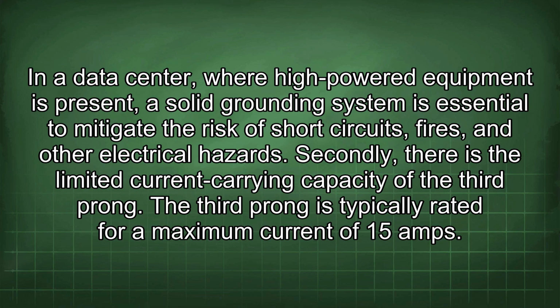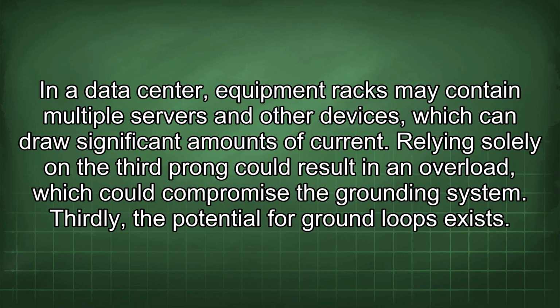Secondly, there is the limited current carrying capacity of the third prong. The third prong is typically rated for a maximum current of 15 amps. In a data center, equipment racks may contain multiple servers and other devices, which can draw significant amounts of current. Relying solely on the third prong could result in an overload, which could compromise the grounding system.